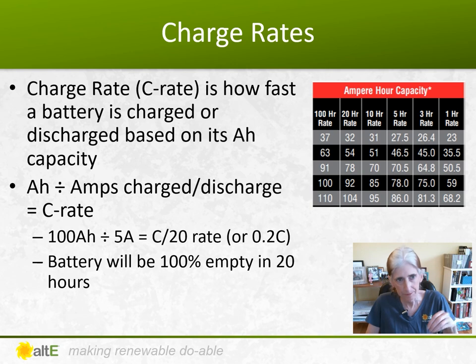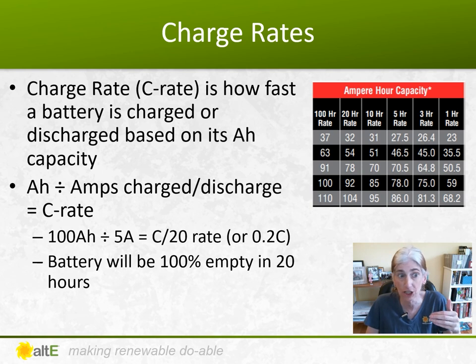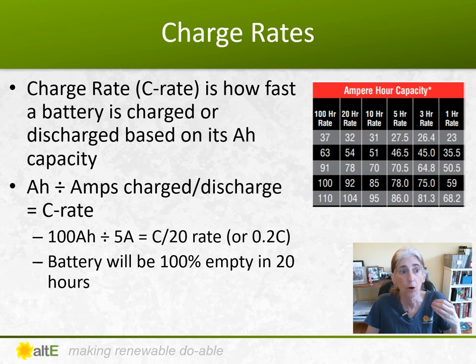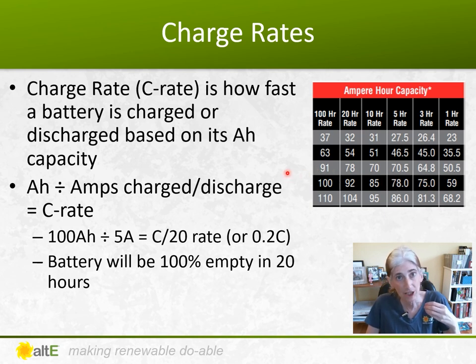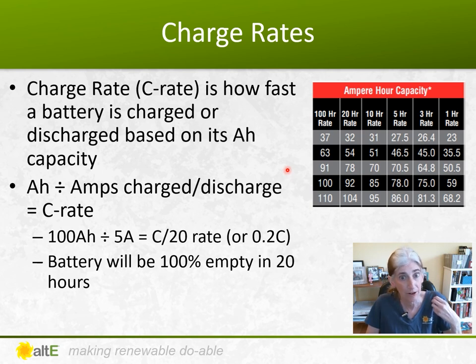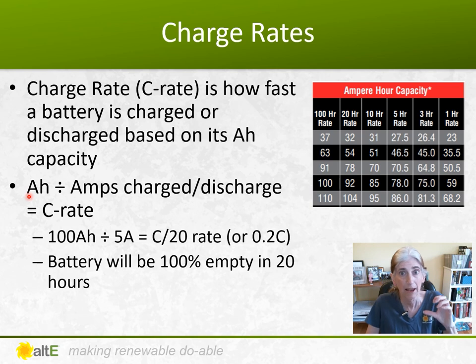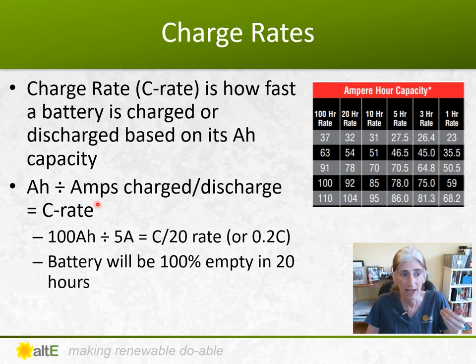A charge rate, or C rate, is how fast a battery is charged or discharged — how many amps are put in or pulled out of the battery. The charge rate is based on the battery's amp hour capacity. It equals the rated amp hours of the battery divided by the amps put in or out. That's your C rate.